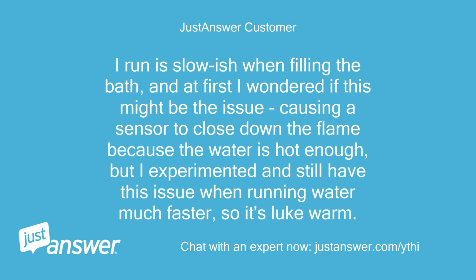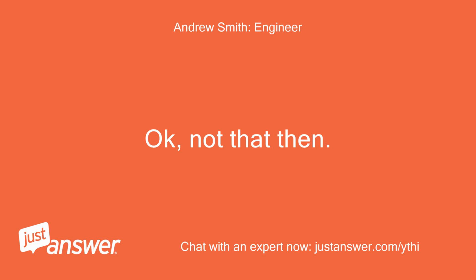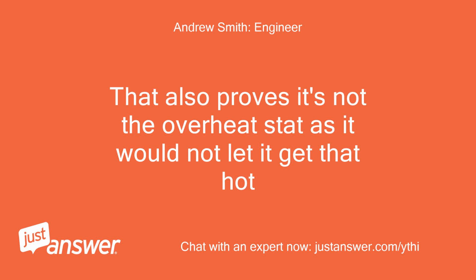I run it slowish when filling the bath, and at first I wondered if this might be the issue, causing a sensor to close down the flame because the water is hot enough, but I experimented and still have this issue when running water much faster, so it's lukewarm. Okay, not that then. That also proves it's not the overheat stat, as it would not let it get that hot.